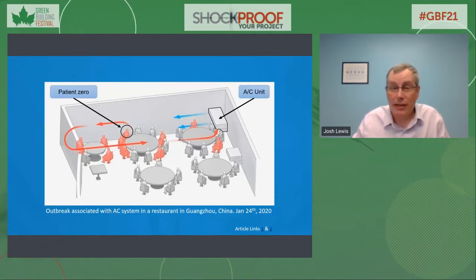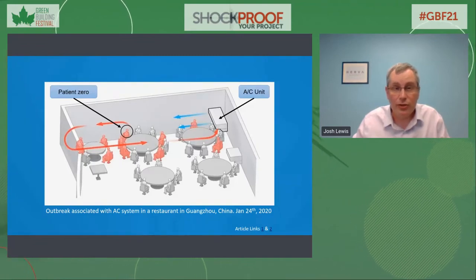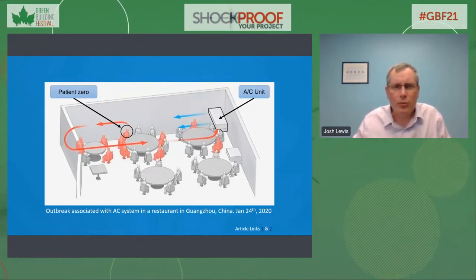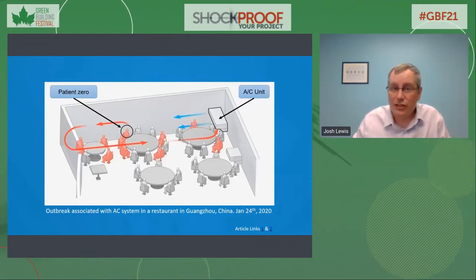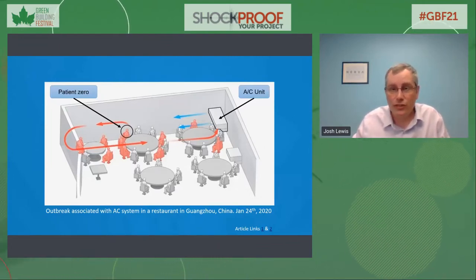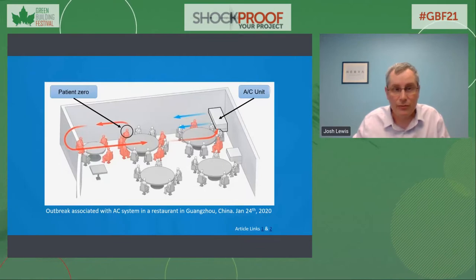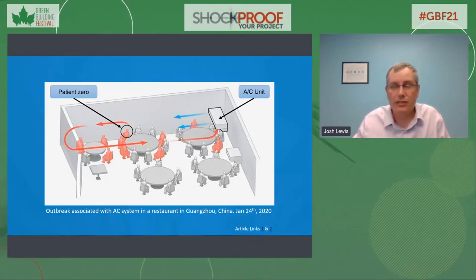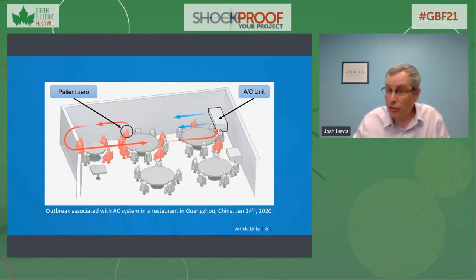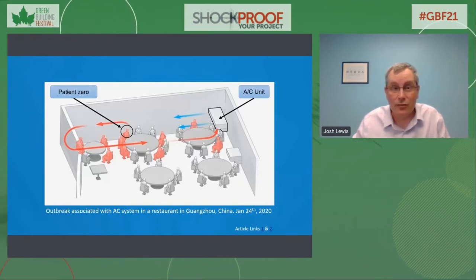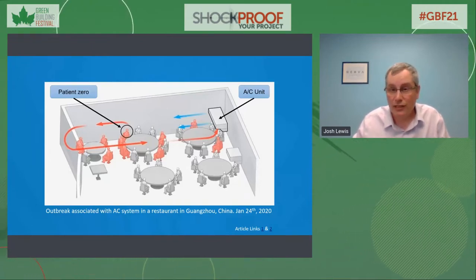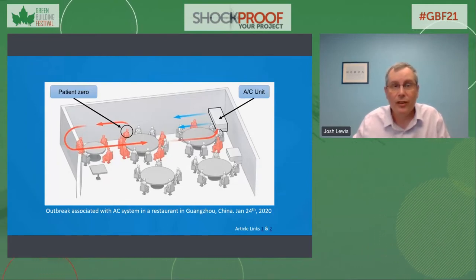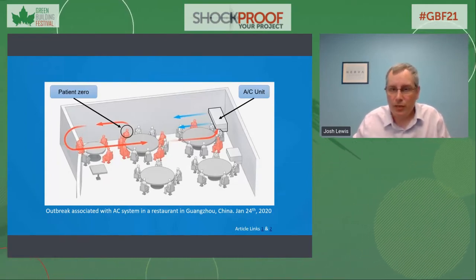In the early days of the pandemic in China, specifically January 2020, there was an outbreak associated with an air conditioning system in a restaurant. As you can see on the diagram, patient zero was sitting at a table on one side of the dining room. On the wall, there was a split system air conditioning unit, which to the best of my knowledge had ineffective filtration, no dilution, as this type of setup typically does not include the mixing of any outdoor air, and there was no purification or humidity.